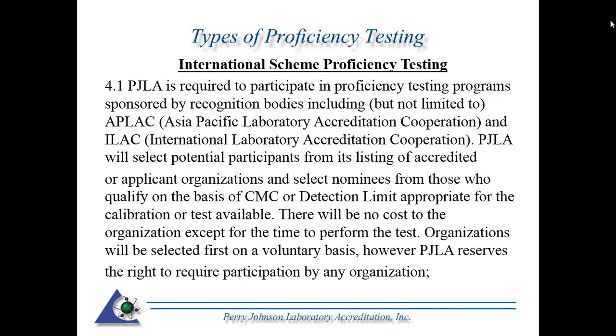We're going to look at different types of proficiency testing. One I want to mention briefly is the International Scheme for Proficiency Testing. This is a line item that's not included or incorporated in the 4-year plan. But PJLA is required to participate in proficiency testing programs sponsored by recognized bodies, including but not limited to the Asia Pacific Laboratory Accreditation Cooperation and the International Laboratory Accreditation Cooperation. PJLA will select potential participants from its listing of accredited or applicant organizations and select nominees from those who qualify on the basis of CMCs or detection limits appropriate for the calibration or test available. These will be at no cost to the organization except for the time to perform the test. Organizations will be selected on a voluntary basis. However, PJLA reserves the right to require participation by any organization.